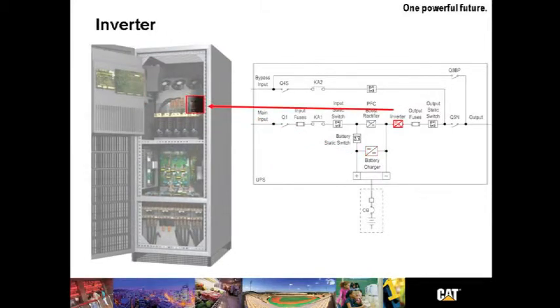The inverter stage is a three-phase inverter with IGBTs and a non-isolated capacitive half bridge. Non-isolated means that there is no isolation transformer, and capacitive half bridge means that we've used a capacitive source, the DC bus, to generate the output voltage through the inverter stage.